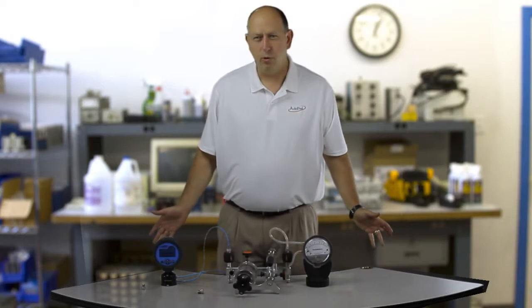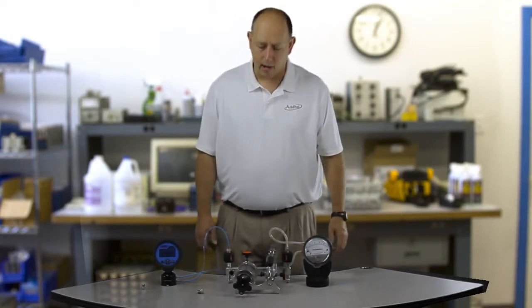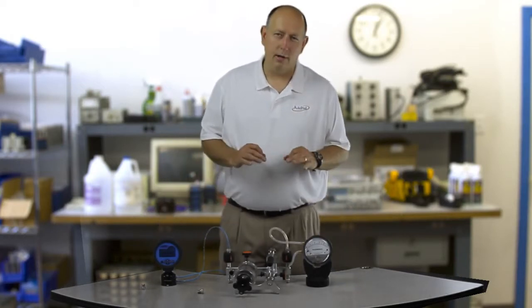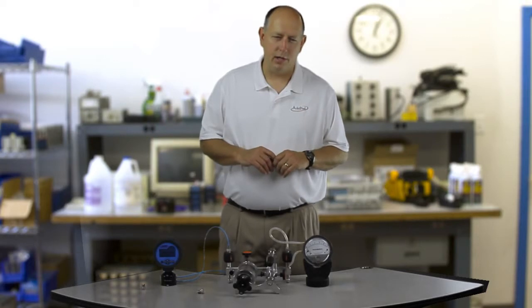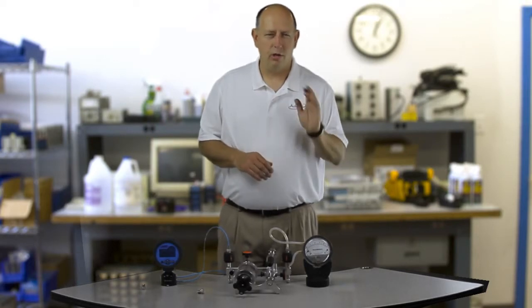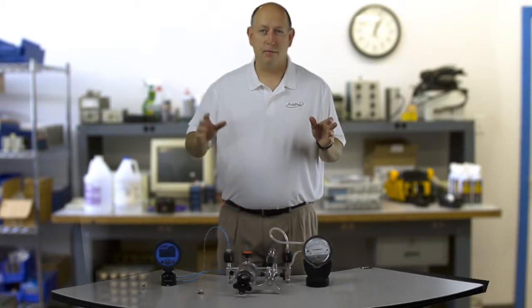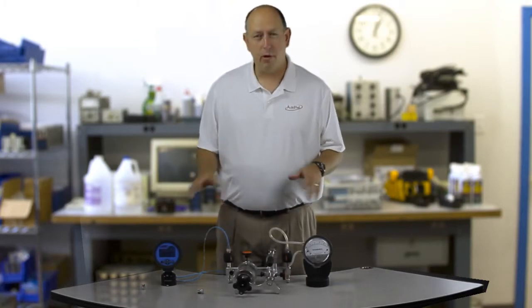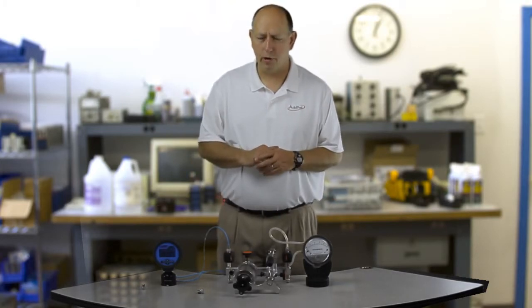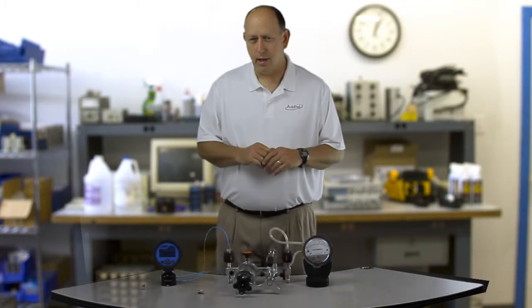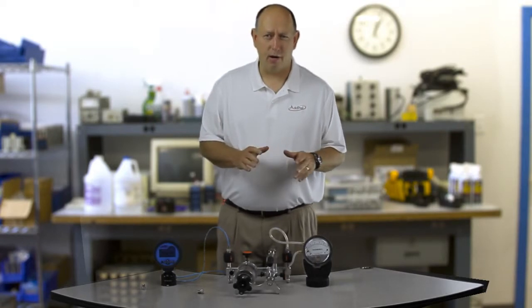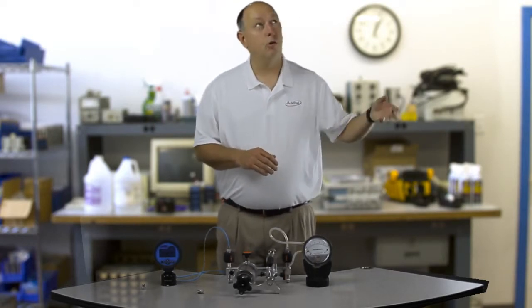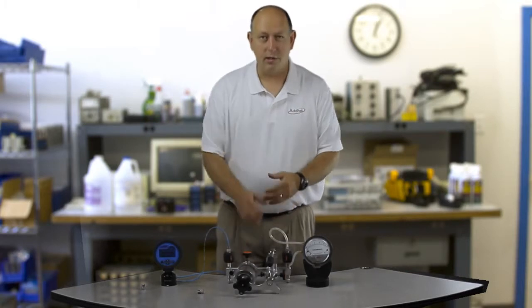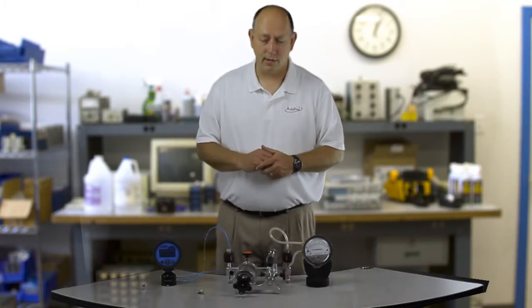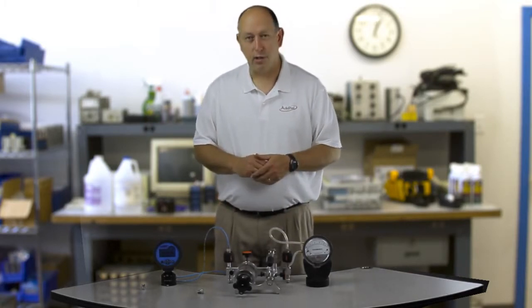Let's do 2 inches of water here to start out with. Those of you who have done low pressure differential pressure calibrations know that controlling past the first digit, reading in inches of water at 4 degrees C, is very hard to control - even the first digit. Anyone opens the door, the air conditioner kicks on, you touch the unit, and it's all over the place. So this is a very difficult calibration to do.